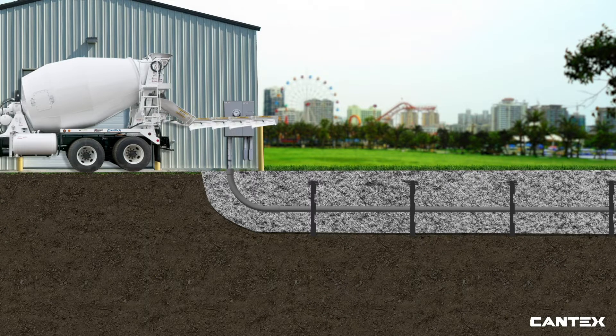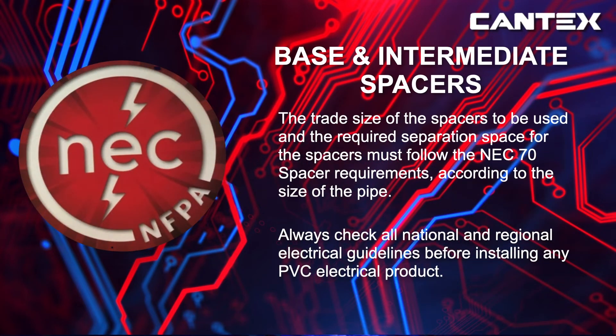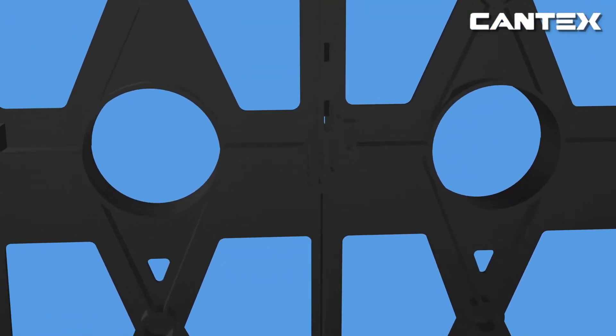This protects the pipe from getting distorted. The trade size of the spacers to be used and the required separation space must follow the NEC 70 spacer requirements according to the size of the pipe. Always check all national and regional electrical guidelines before installing any PVC electrical products. Cantex base spacers simply slide in place and lock together — no tools are needed.